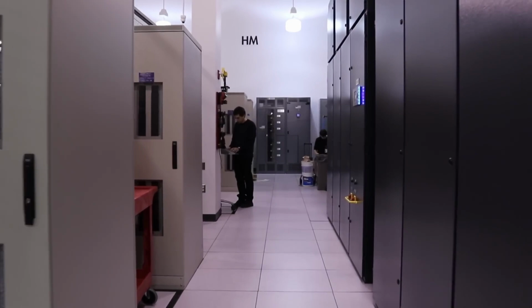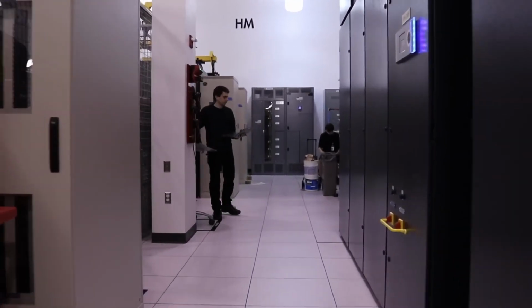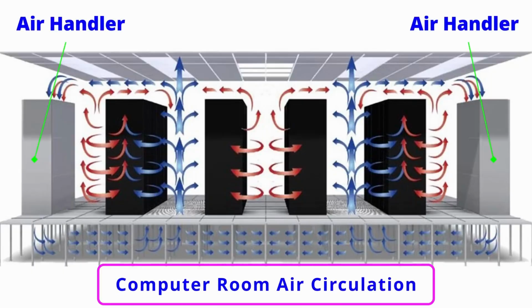It has to run coolant all the way through the perimeter of the room because each of the computer room air handlers don't have compressors on them. They're just big radiators taking that hot air, pulling it through the radiator, cooling it down with the coolant, then pushing that coolant right back this way.